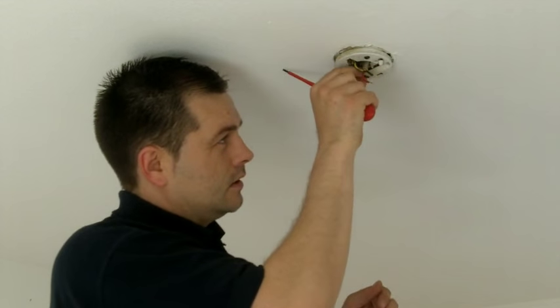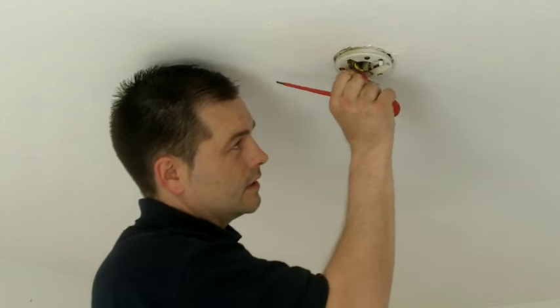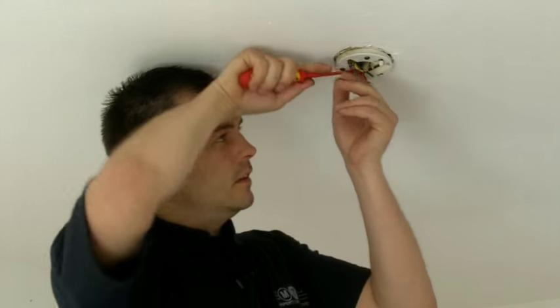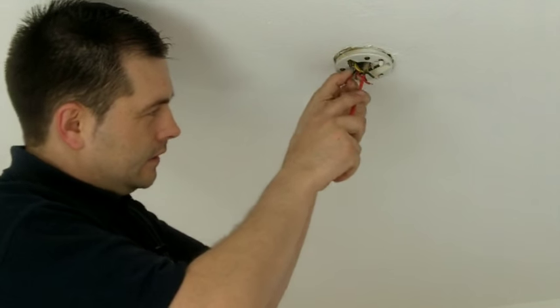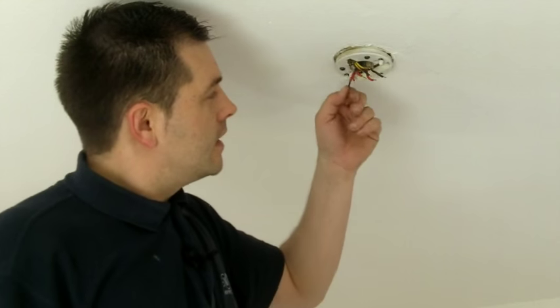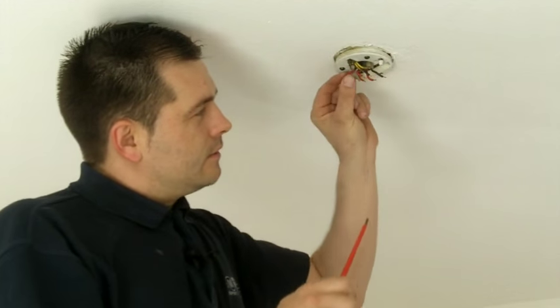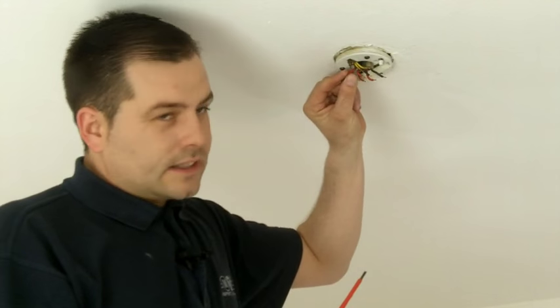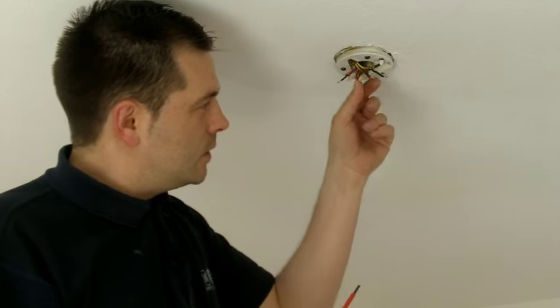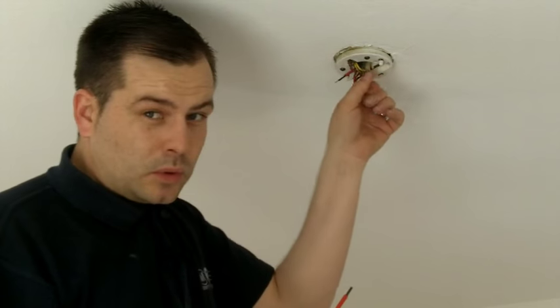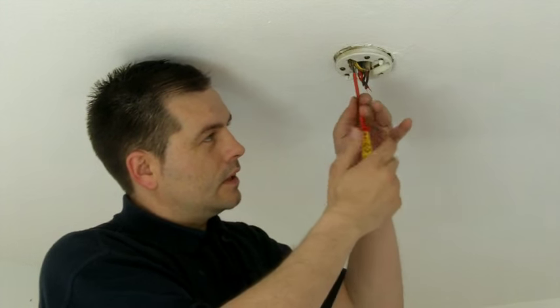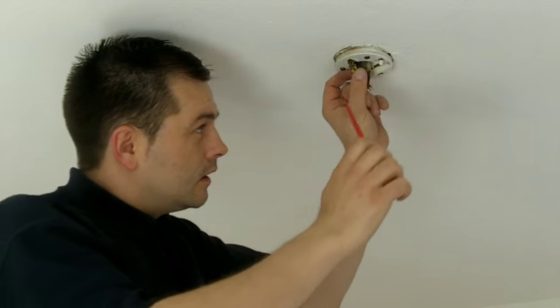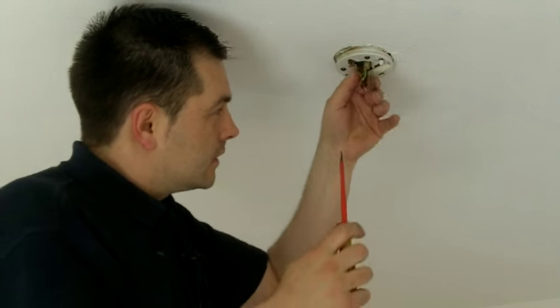So if we first remove the cables from this existing terminal you can then see that one of these black cables, which may also be blue in the newer homes, one of these black cables will be identified with a red sleeving. Now this is to show that this is the live cable that activates your light fitting and carefully remove the earths.